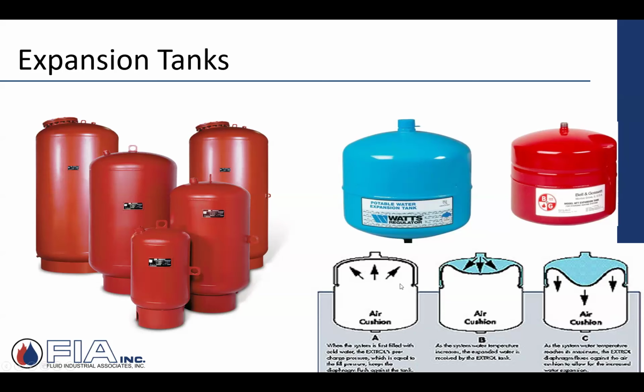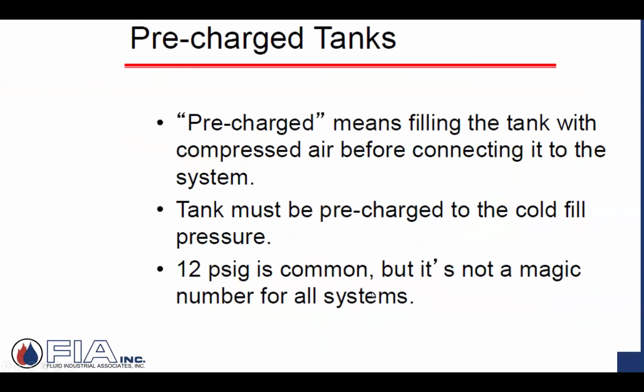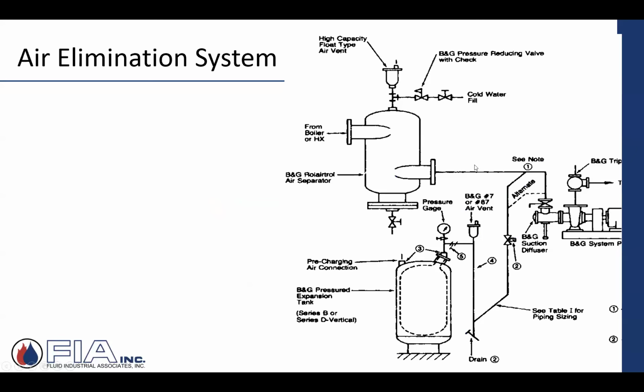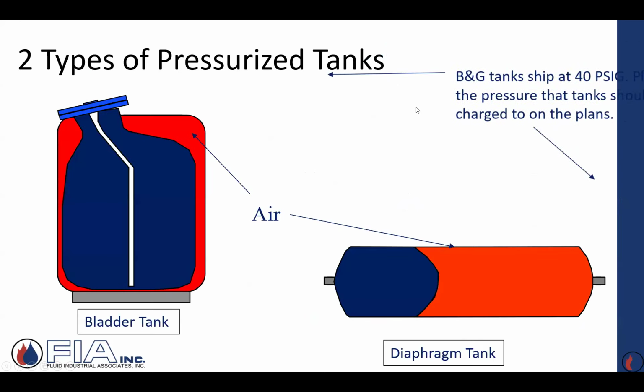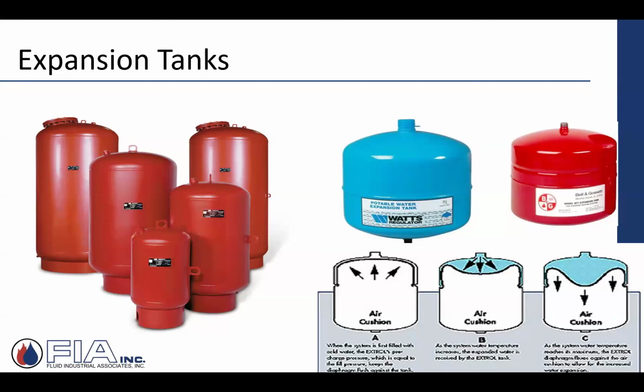We just need to understand, when I install it into a system, that's why I keep saying that the pre-charge in that tank has to match whatever my fill valve, my pressure reducing valve, is set for, so that they work together. So when I attach it, it looks like that. There is no water in those tanks until such time that you turn the boiler plant on and you heat the water. Now, as it expands, again, water is not compressible. The only place it can go is where I have this body of air. Air is a gas. Gases are compressible. That's where it will go. It'll squeeze that cushion.